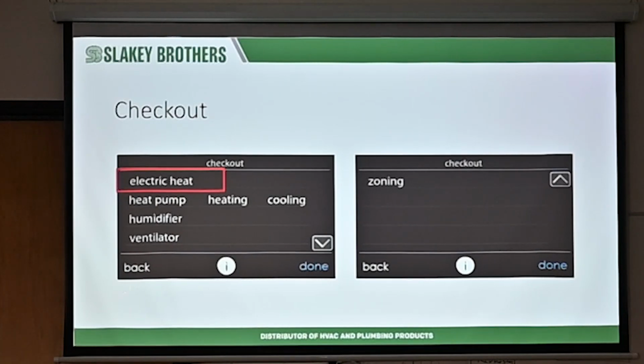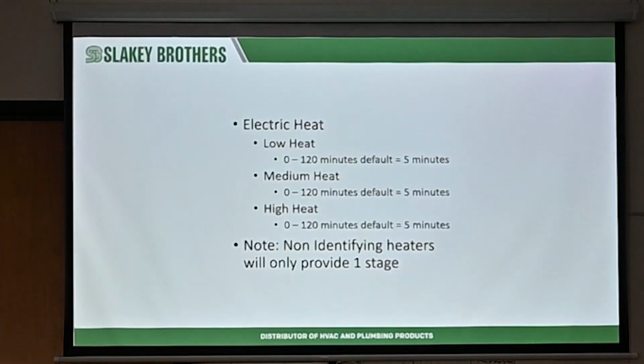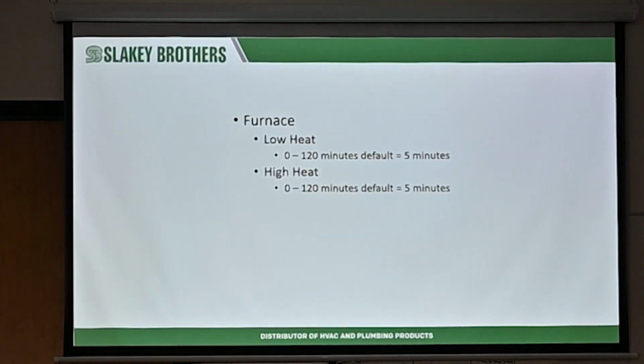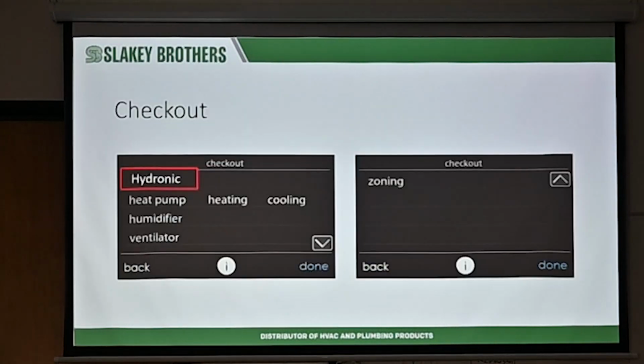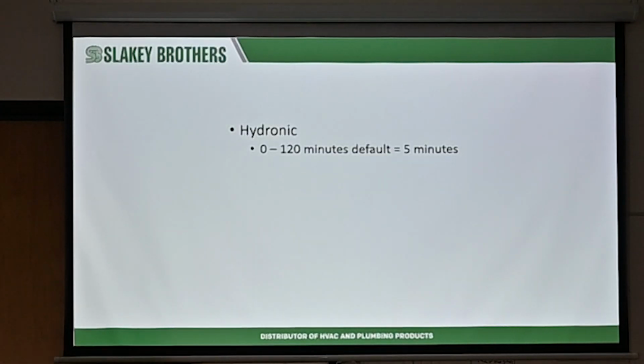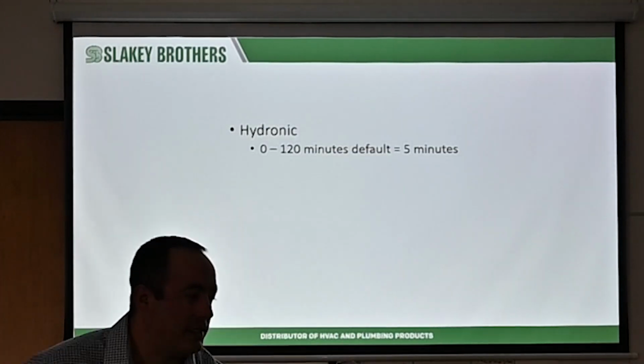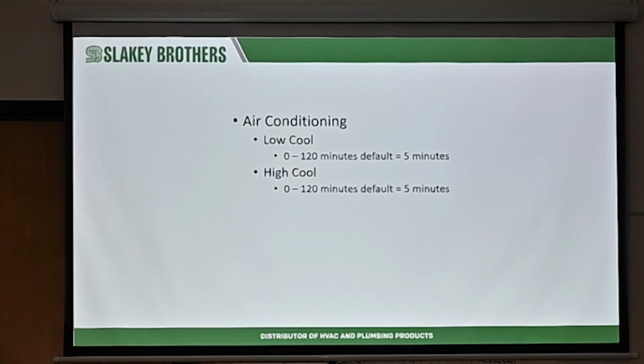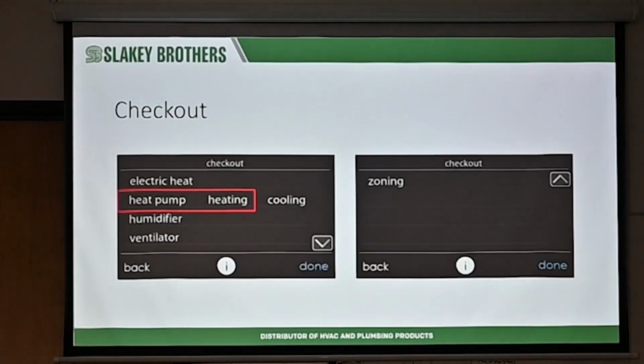You can check your humidifier out, or even activate the ventilator if it can control a ventilator, because there are some ventilators that can be controlled off of a zone board, but we're not going to get too crazy into that one. But this is where you can check out all your different features of it. And it tells you your time. Same thing, checking out your furnace, low or high, or if it's modulating, it'll modulate on its own. Hydronic, same thing. You're just going to tell it how long you want the hydronic system to test for. And even the air conditioner. Again, all you're doing is forcing that unit to come on in that mode, so you can check it out.